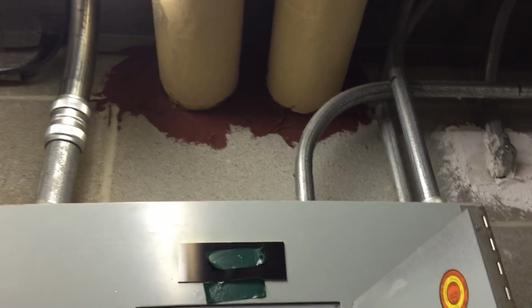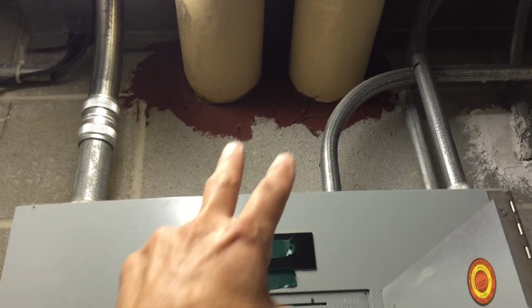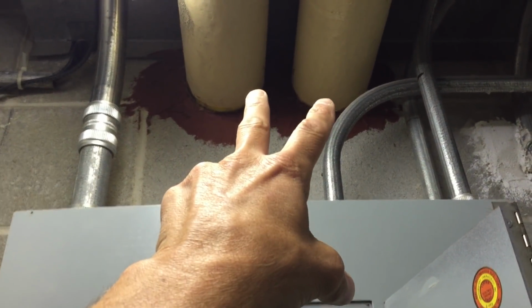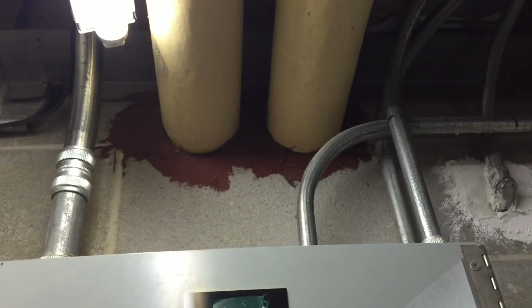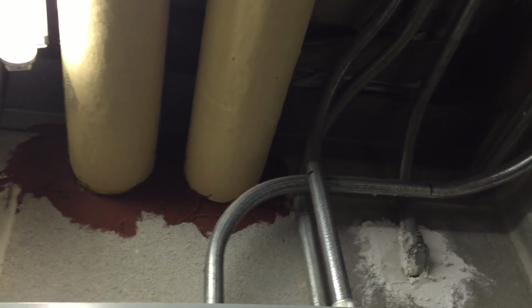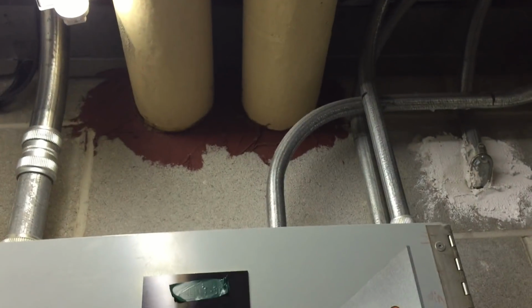No foreign systems are permitted. But here we have these two, I'm assuming they're heating pipes, seeing how they're insulated. And above that is ductwork passing by. It might be a little hard to see. So we have two foreign systems located directly above this panel board.